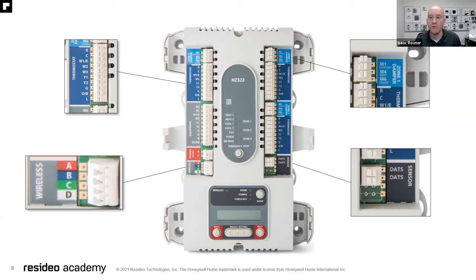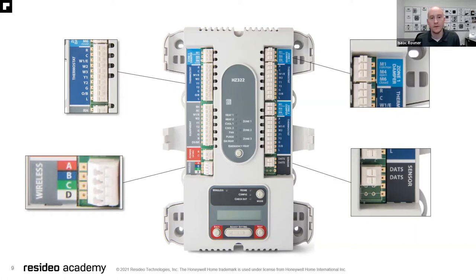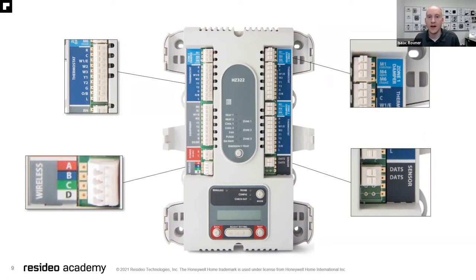We can wire M1, M4, M6 — typically our dampers are spring open, power closed, but some of our products allow you to modify that to power open, spring closed, or power open, power closed, so you do have some flexibility there. What's not enlarged here is our equipment wiring, which is on the left side where that gray terminal box is — that's where you wire the HVAC equipment.